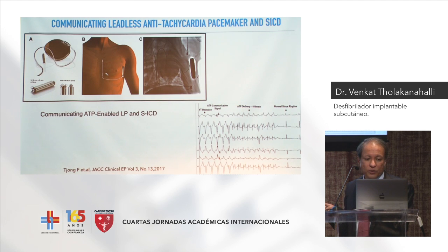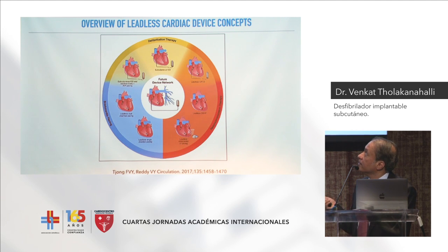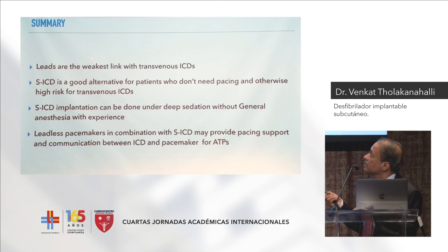So the future is, you saw this slide earlier, combining the SICD with a leadless pacemaker, so you can communicate between the two using Bluetooth technology, as well as having pacing when they need it, whenever there are bradycardia reasons, or you can even deliver the ATP. That is one of the things being studied now. And this slide was also shown in the previous talk, the SICD in combination with CRT as well as defibrillator. So in summary, leads are the weakest link with transvenous ICDs.